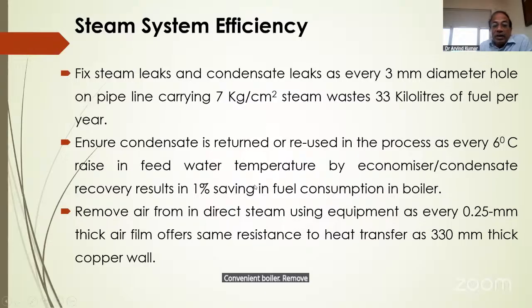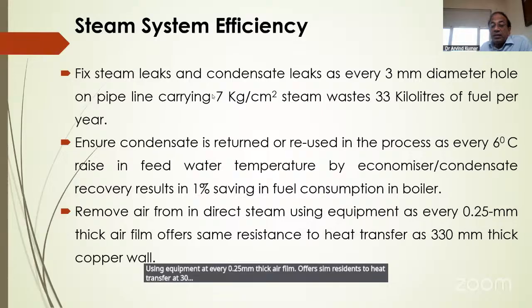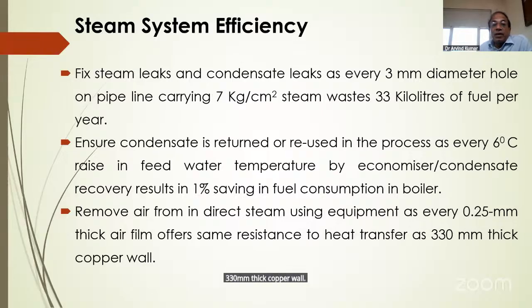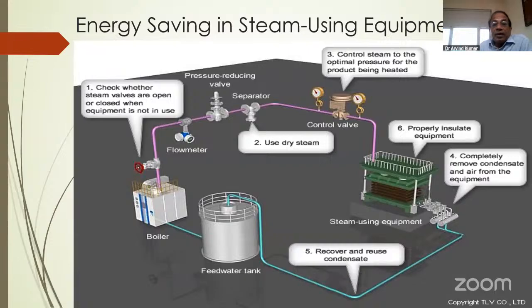Remove air from indirect steam using equipment, as every 0.25 mm thick air film offers the same resistance to heat transfer as 330 mm thick copper. So if there is any air trapped, it provides high resistance and hinders the transfer of heat, and that leads to a very high energy loss and overheating of the system. So it reduces the life of the plants and of this line, and it also reduces the energy use or power generation. So that is the energy saving in steam using equipments.